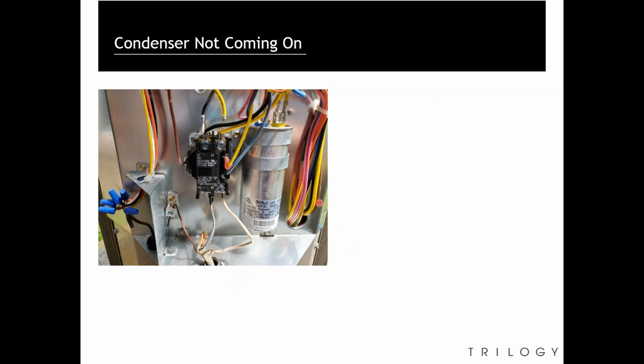So if our condenser is not coming on. Now, before we remove the panel on an air conditioner, make sure you pull the disconnect to prevent shock. Now, is the contactor, is it sucked in? Do we have that 24 volts?